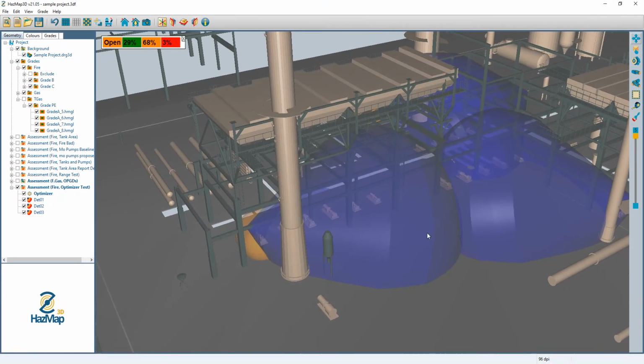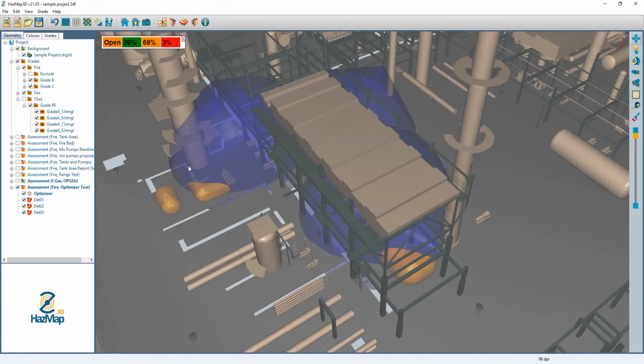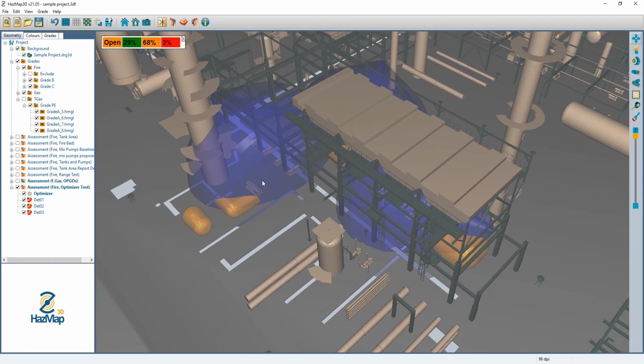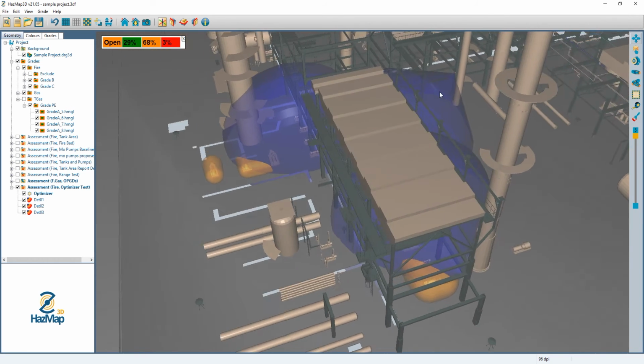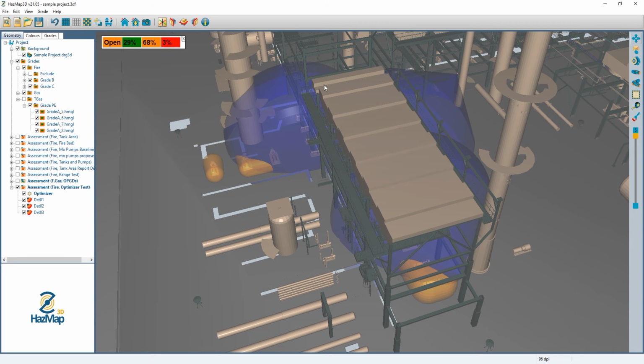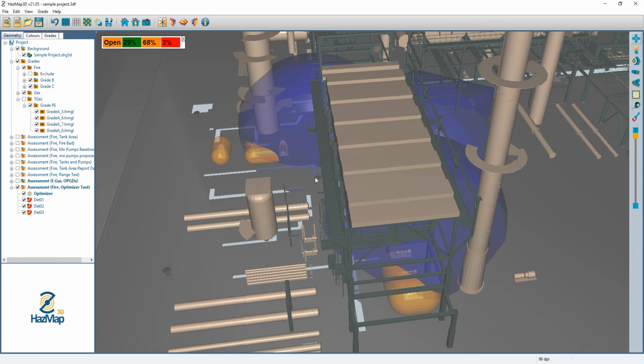So we can see that we get a result after a couple of minutes here that is basically in line with what I was expecting. We've got a detector back here, a detector over here, and a detector on the side group of posts, and it's using each one of those 3 surfaces that I gave it the allowance to mount the detectors to.